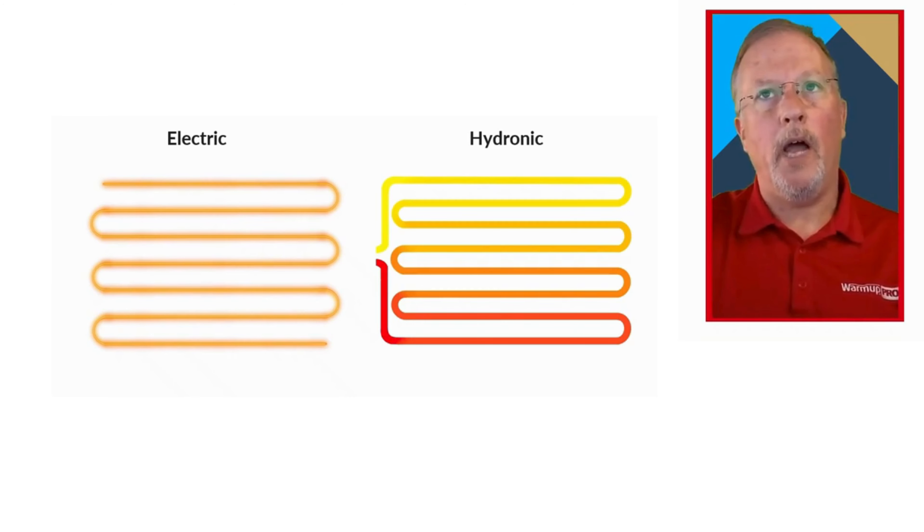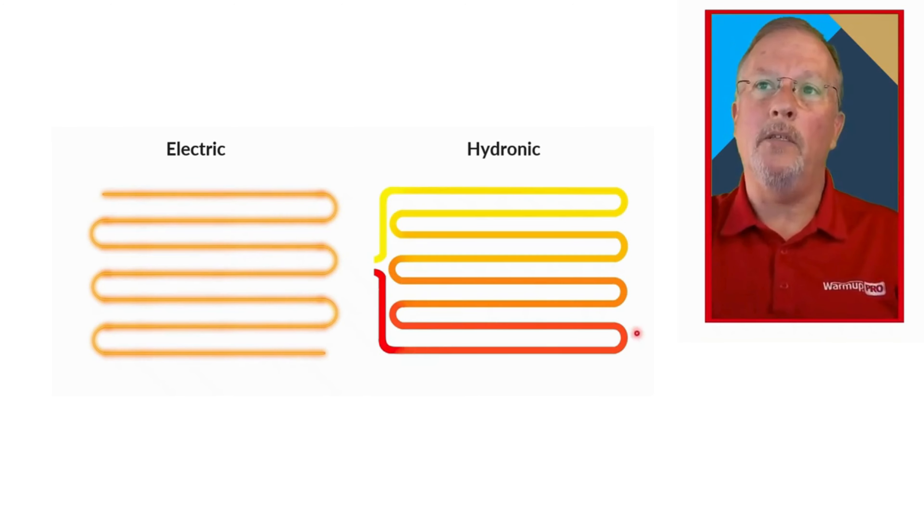This is illustrated here on the hydronic side. Notice how when we come in with a hydronic system, the water enters the piping system in the floor at its highest temperature, typically around 140 degrees Fahrenheit. But as it starts traveling through the floor, it begins to lose the heat until it leaves and returns back to the boiler system, where it can be reheated again, and the cycle starts over.